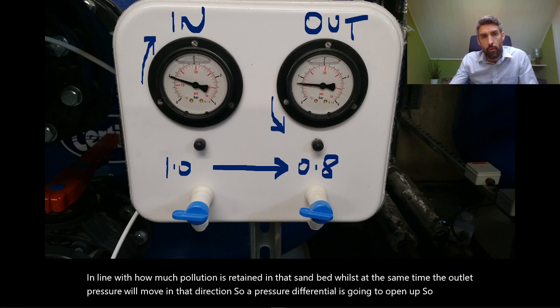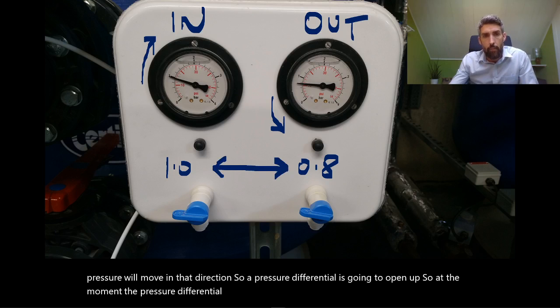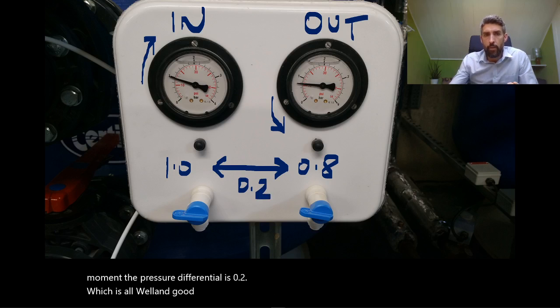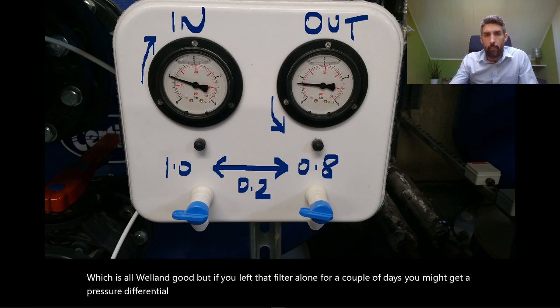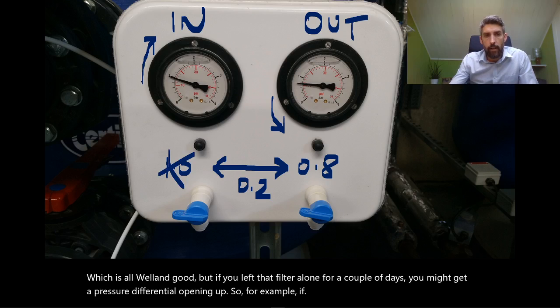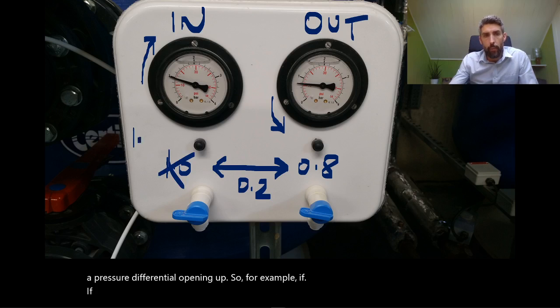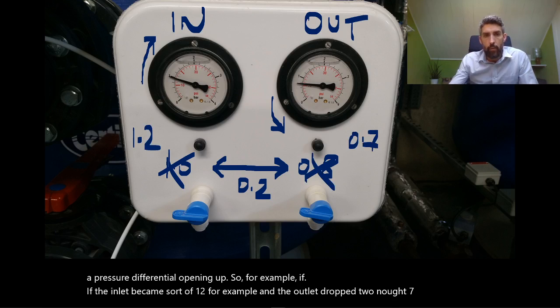At the moment the pressure differential is 0.2, which is all well and good. But if you left that filter alone for a couple of days, you might get a pressure differential opening up. For example, if the inlet became 1.2 and the outlet dropped to 0.7, then we're dealing with a pressure differential of 0.5.